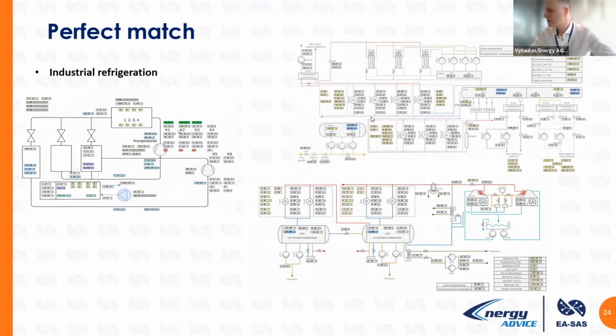Three examples of quite different setups: for example, two compressors on one stage and two other compressors working on another stage, and condensers, and we deliver cold chilled water and minus water, -2, with ammonia or CO2. Another example is three compressors working in minus, it's CO2, I remember this example. Three compressors working at -40, four compressors working at -10, chilled water, economizer installed, and then a condenser. And as shown earlier, the Rokiškio cheese producer with four compressors on chilled water and two compressors at -20.